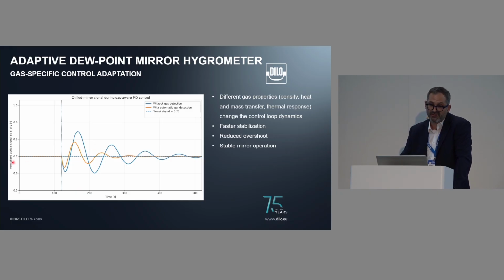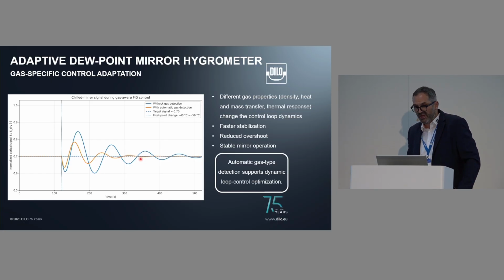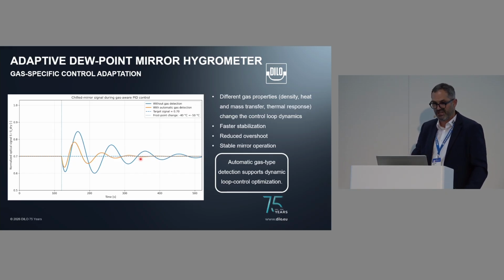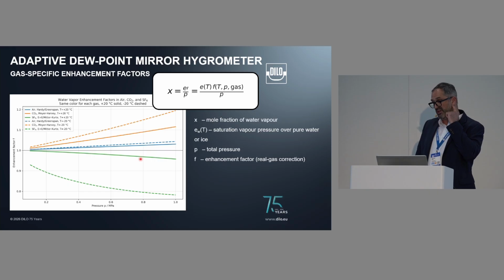changes. What you see here is a normalized optical signal. That means it is a reflection value divided by the reflection value of the clean mirror without condensation on it. For each gas you can optimize this control feedback, and the positive effect is a faster stabilization time. So automatic gas detection supports dynamic loop optimization. With automatic gas detection, you can also display the correct values.